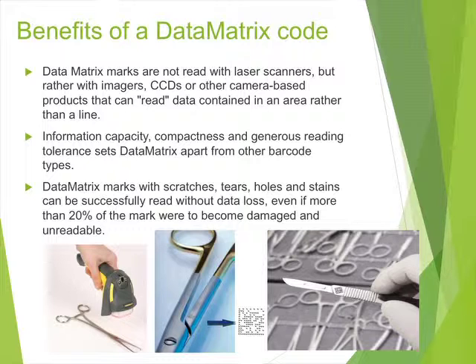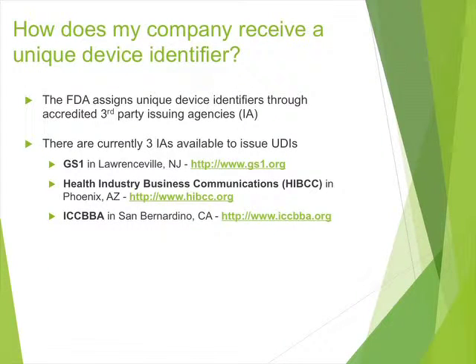Another benefit of data matrix codes is that directly marking them on a device doesn't alter the ergonomics of the tool — it doesn't impact how a surgeon or user will touch and interact with the device. To receive a unique device identifier, you work with one of three issuing agencies: GS1 in Lawrenceville, New Jersey; HIBCC in Phoenix, Arizona; or ICCBBA in San Bernardino, California. These companies will help you navigate and begin receiving the unique device identifier.